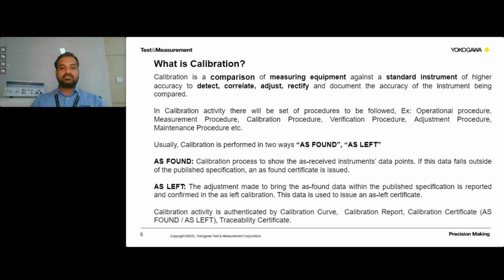Usually the calibration activity is authenticated by a calibration curve, a calibration report, a calibration certificate provided by a NABL accredited lab, and finally a traceability certificate. These are the reports or set of documents which authenticate the calibration activity.